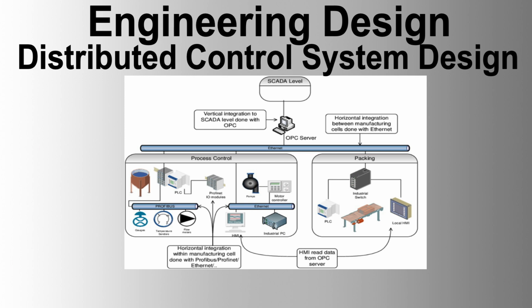2. Serial I/O interfaces. All I/O must be repeated to the DCS via dual redundant serial links, including all ESD, F&G, compressor UCP, power generation, switchboard, and packaged unit I/O with system diagnostic information. The serial communications protocol must conform to the existing system standards, using a specified baud rate and Modbus RTU format. The DCS must fully control all remote systems with the same functionality as local panels, capable of startup, maintenance overrides, and equipment trips over serial links.